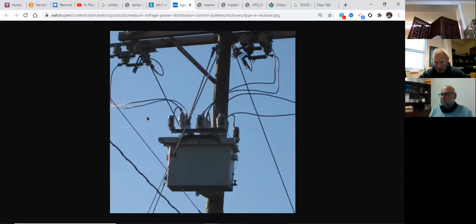If a fault occurs beyond the recloser, which is about halfway between Conway and Loris, I want to sectionalize, or take out of service, one half of that line, and keep the other half, the half coming from the breaker, on.